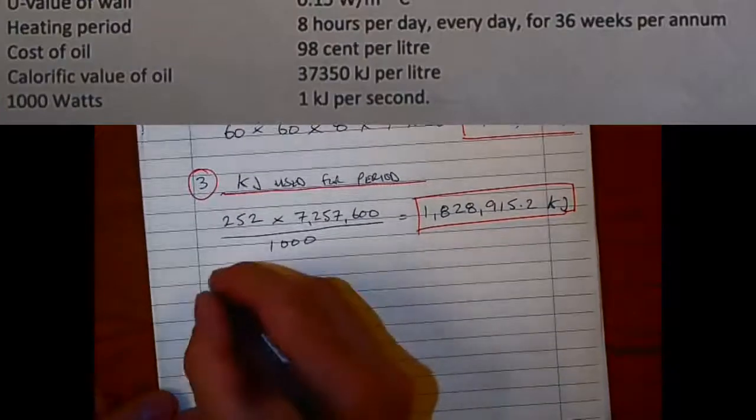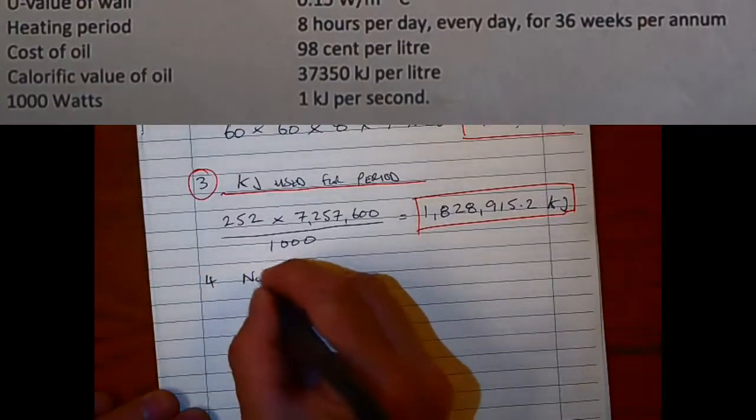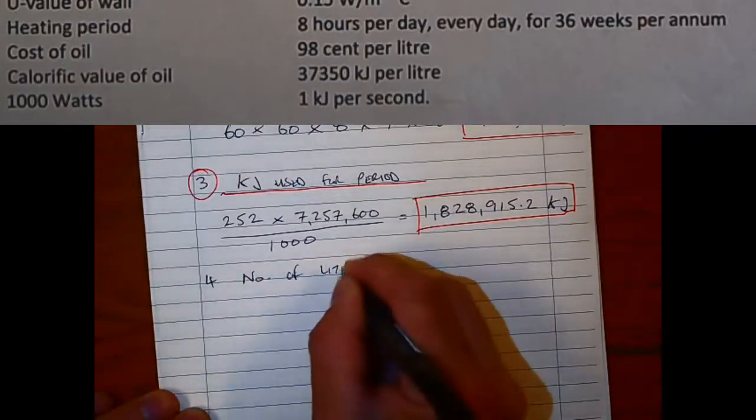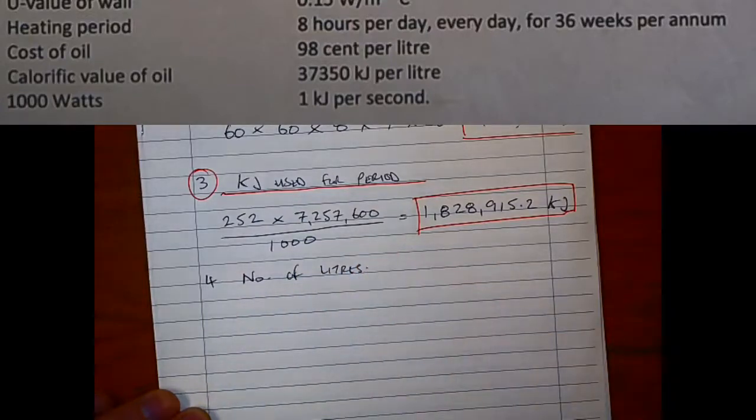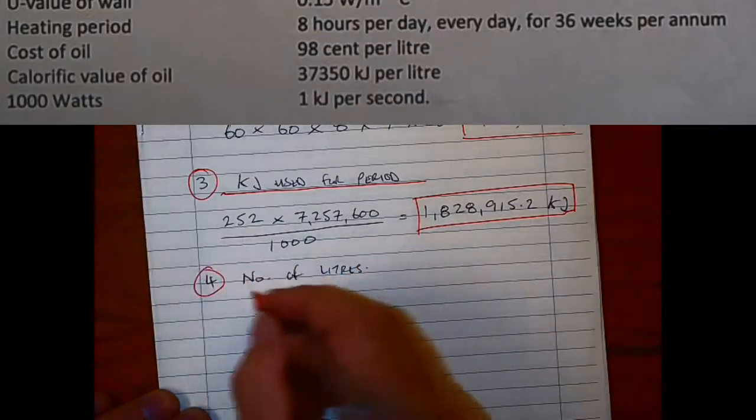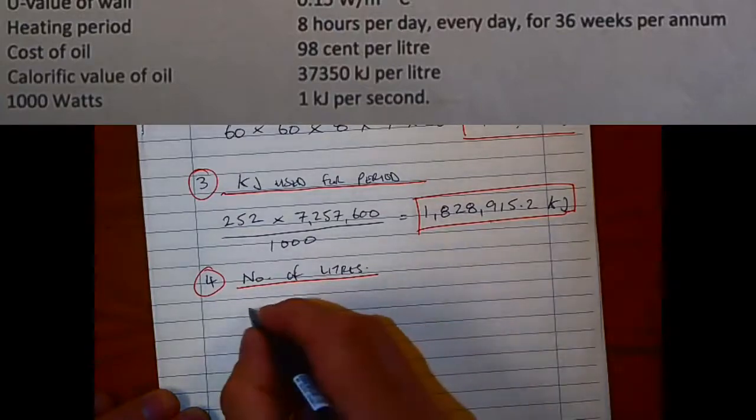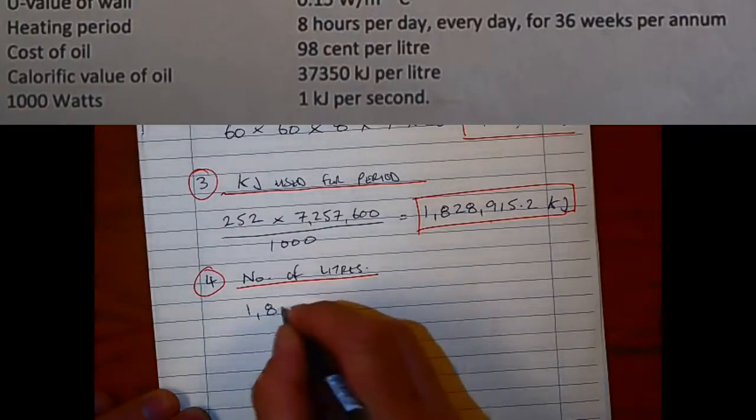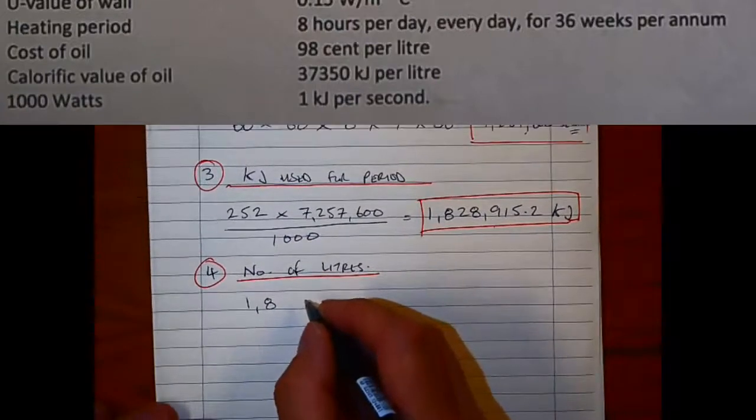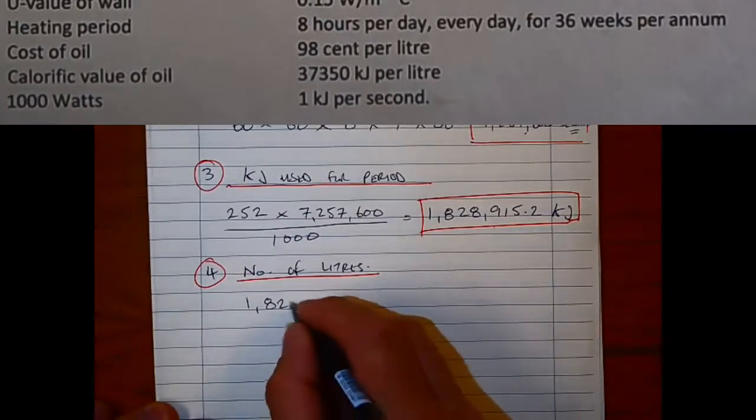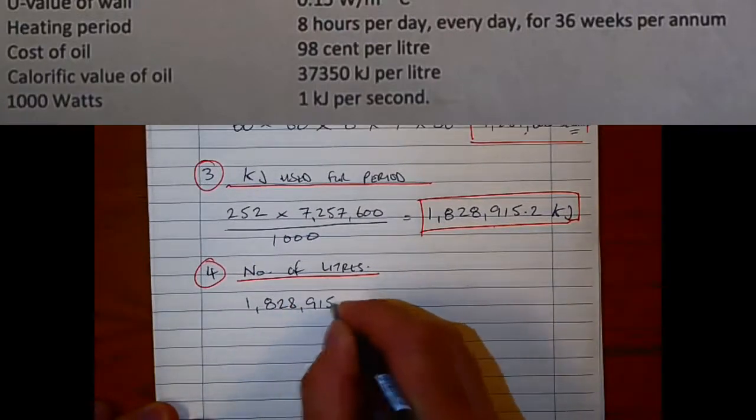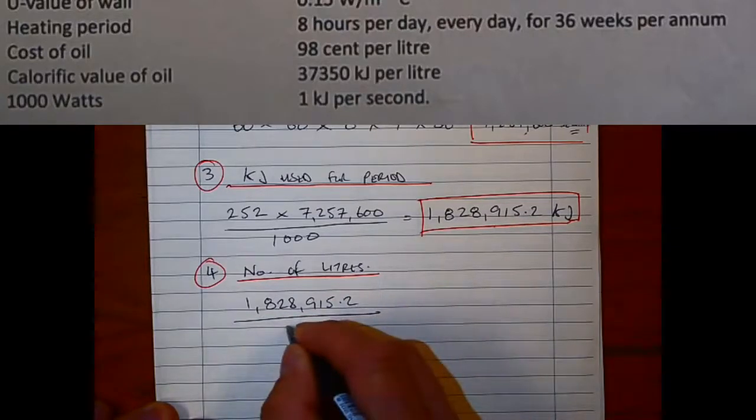You'll see now from the other second half of that part of the question here, I've highlighted it here again—you've got to look at the calorific value of oil above here to work out the number of liters. We're told it's 37,350, which is normally fairly standard as it's used. We're going to divide our number of kilojoules for that heating period by the 37,350 to work out how many liters that we have. So we're calculating the number of liters.